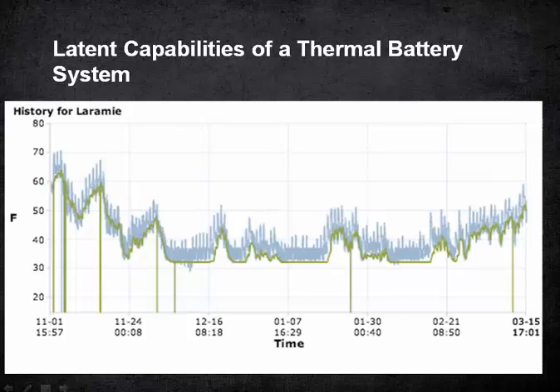You can see four dead flat locations there, where the green line is the thermal battery and the blue line is the transfer tank — you'll see a schematic of how this looks after. Those dead flat lines are when it's acting like 357,000 gallons; it's very difficult to deplete it. You can see in the first bit of December there, those are where the blue line is dipping under the green line. That's when the battery has got ice all over the heat exchanger, the loads are extreme, and the heat pump is serving those loads.